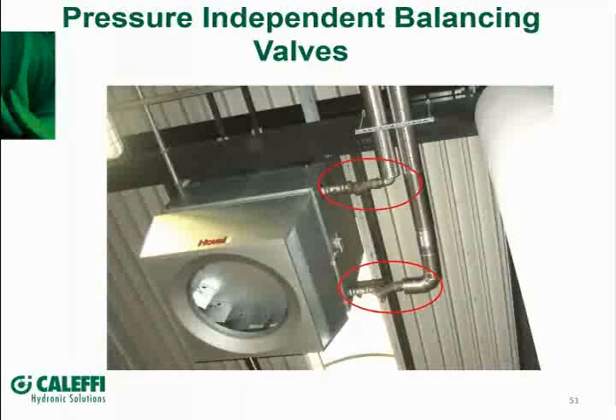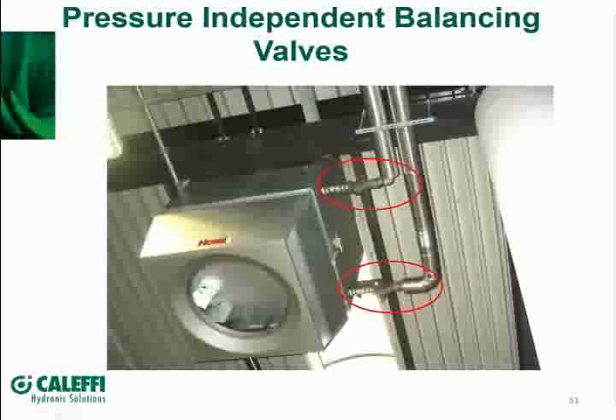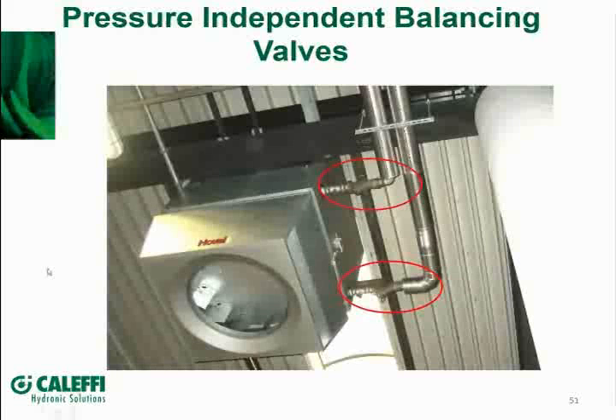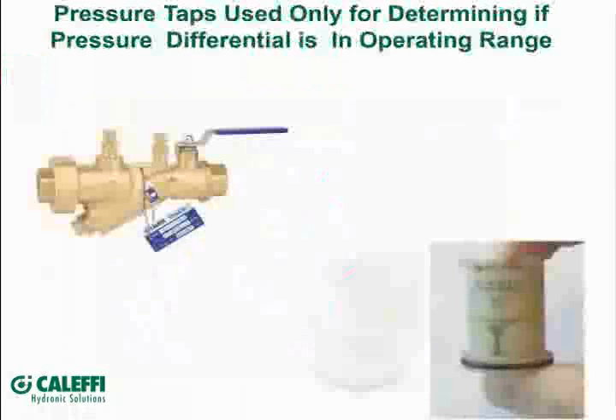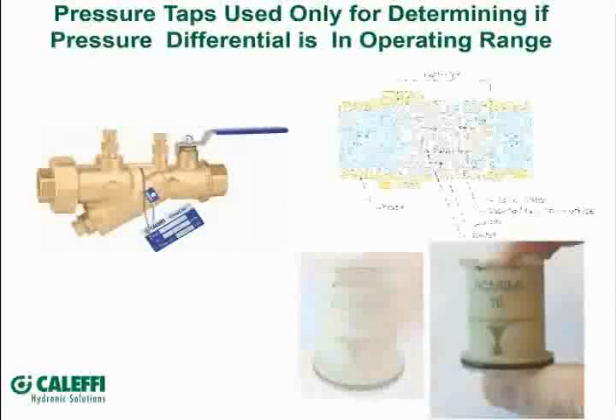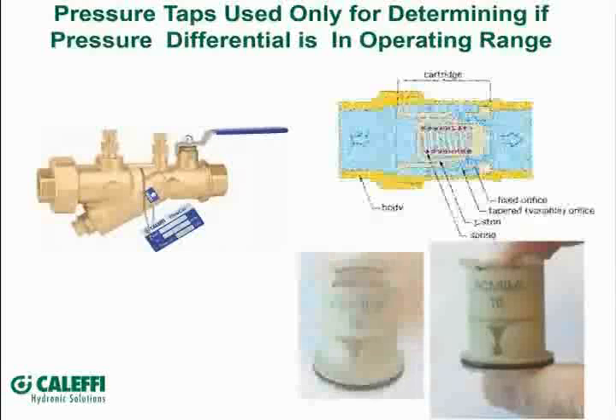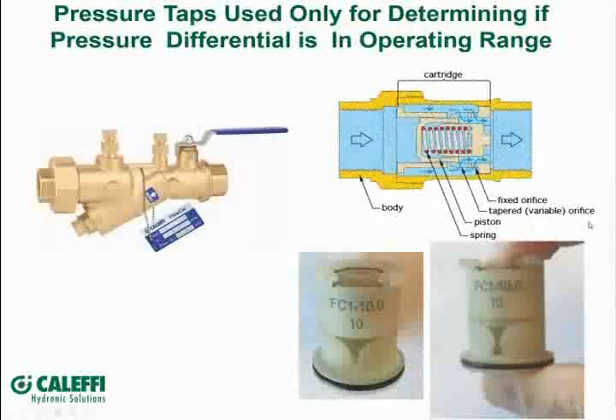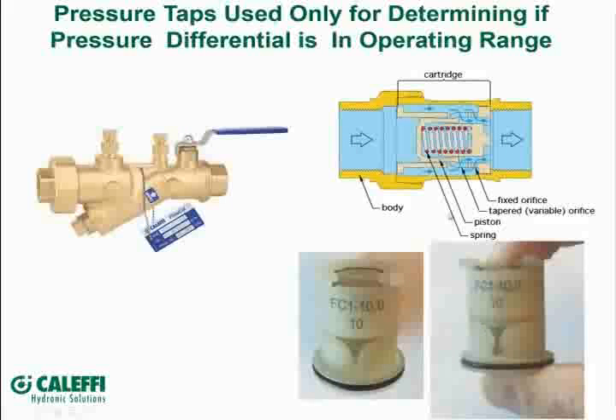The question becomes: are there products whose CV value can change as operating conditions change? Yes — this is our 127 valve. It is built differently inside with a pressure-independent balancing mechanism, used in applications where you want to make sure your flow rate stays consistent regardless of what's going on in the system pressure.